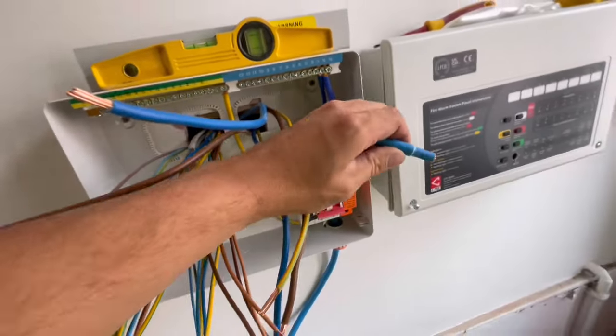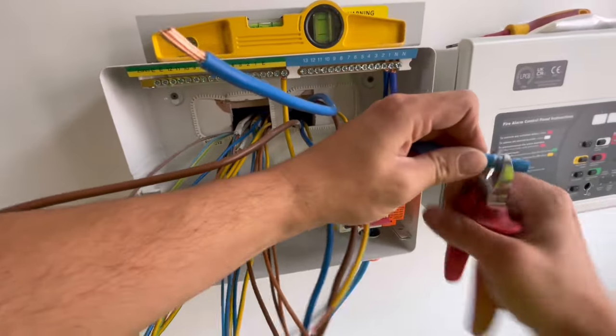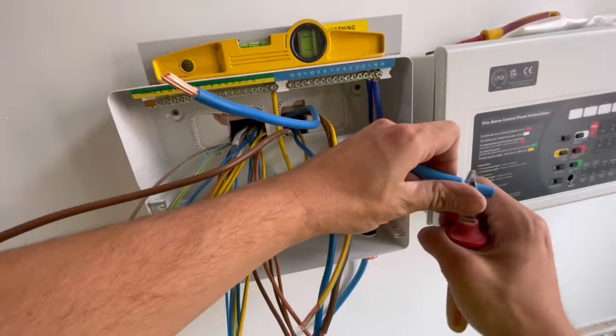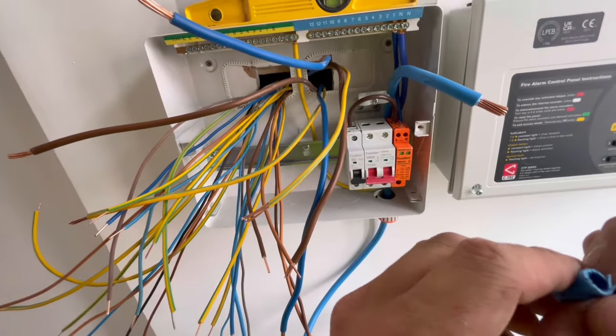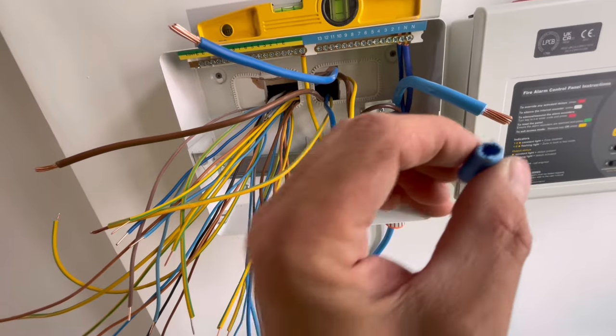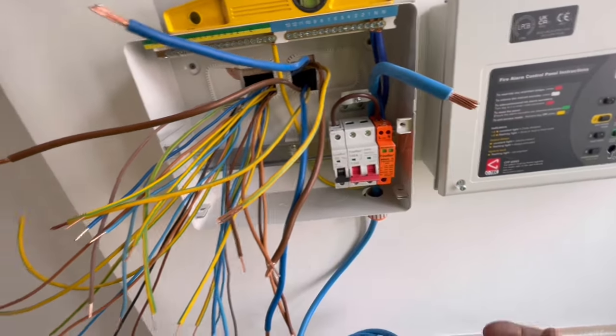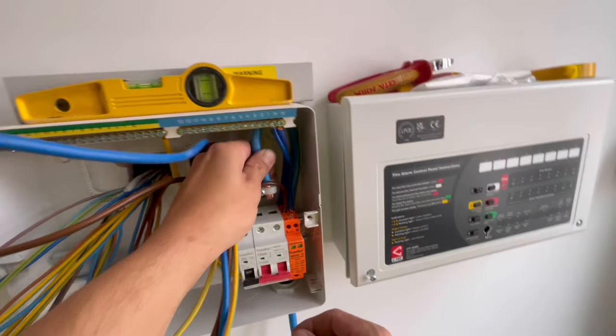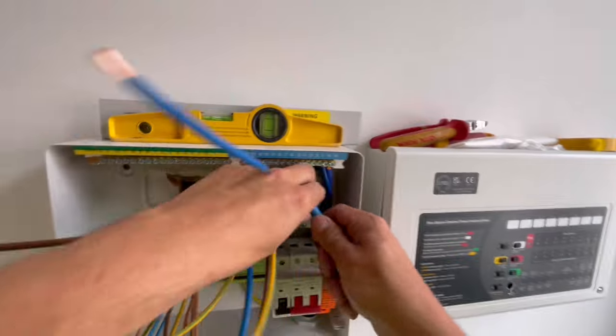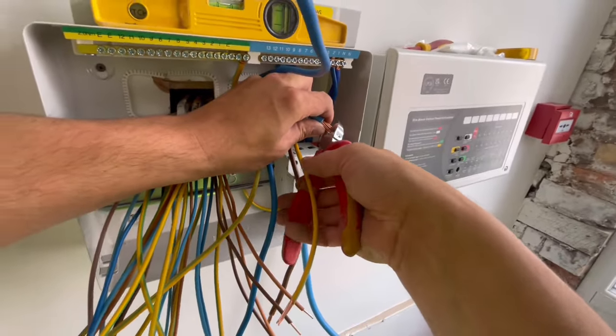You can see this is what's called double insulation. I'll show you, this is the main power coming in. You can see how thick that is, and you've got two of those because we don't want anything touching this, as this is permanently live. Well, I can see there I can probably take another few mil off this copper end, and also with a bend it'll be a different length.